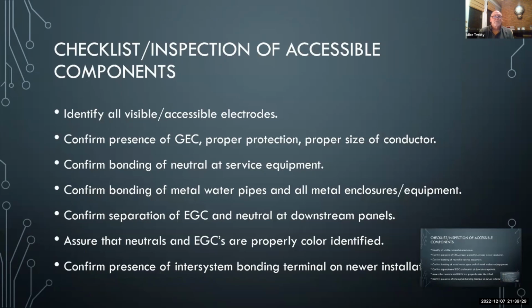Okay, here's a little checklist of accessible components. Identify all visible and accessible electrodes. Confirm the presence of the grounding electrode conductor, proper protection, proper size. Confirm bonding of the neutral at the service equipment, and confirm bonding of metal water pipes and all metal enclosures and equipment. Confirm the separation of the equipment ground and the neutral at downstream panels, sub panels, anything downstream of the service. And ensure that neutrals and equipment grounds are properly color identified. Confirm the presence of the intersystem bonding terminal at all newer installations. And I think that's all I've got.